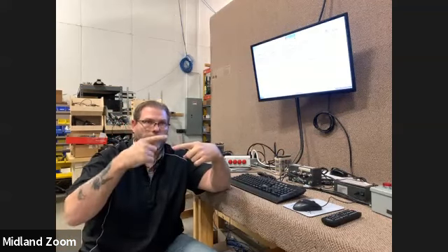So you can hardwire in the pause buttons, or in the case of the case packer or the stretch wrapper, you could have a photo sensor monitoring something that's turning. And then as soon as that's not turning anymore, you can wait a given time, hit an output to the shrink wrapper, to their pause.